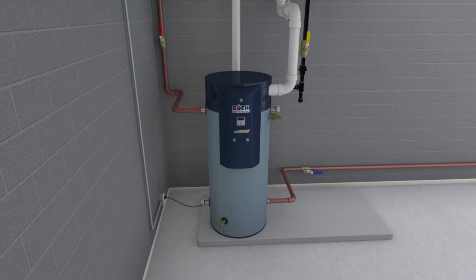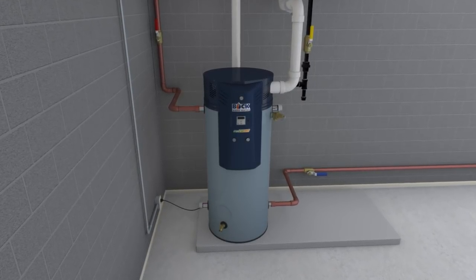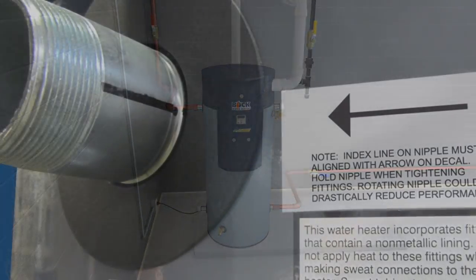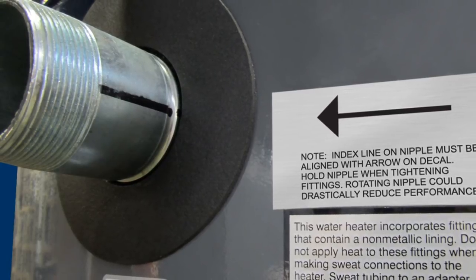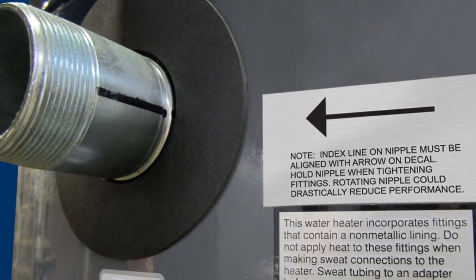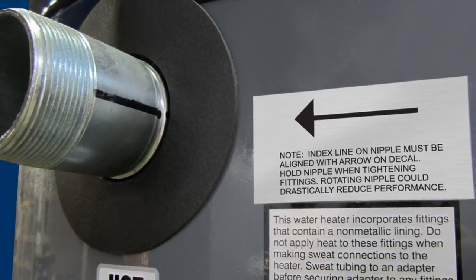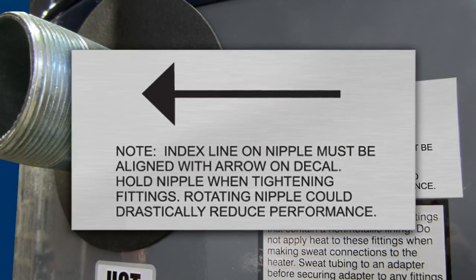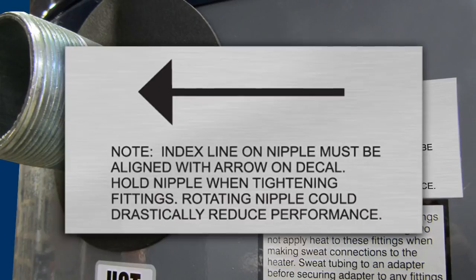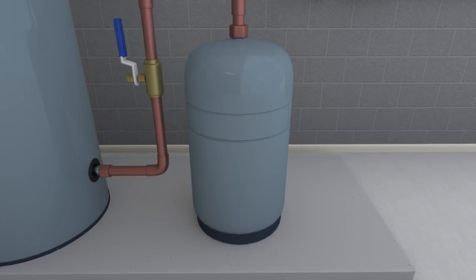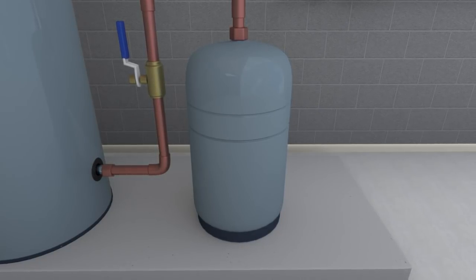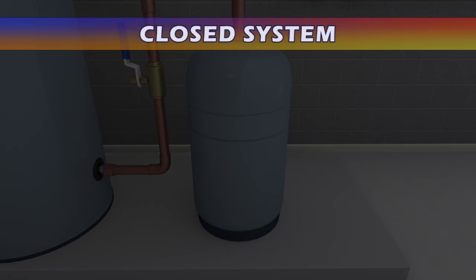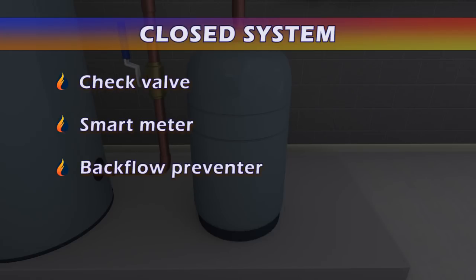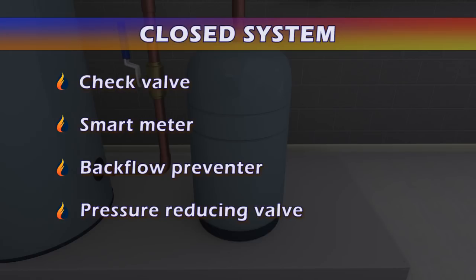If power is to be removed for an extended period, the water heater must be drained. The pipe nipples at the hot outlet connections are factory installed and must not be rotated when connecting fittings in the field. If the orientation is changed, there will be a reduction in water heater performance. Be sure an appropriate expansion tank is installed if the water system is closed. A system is considered closed if it includes a check valve, smart meter, backflow preventer, and/or a pressure-reducing valve.